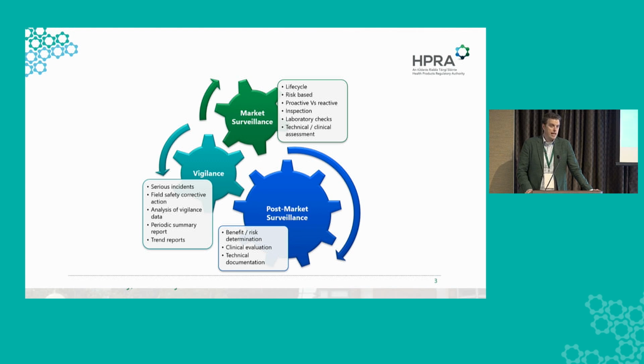So this is really how the manufacturer monitors the performance of their device once it's on the market. It really should be taken as a life cycle approach over the entire lifetime of the device. So it needs to look at the device from end to end, from day one that it enters the system to the day it leaves the system. And it needs to feed back into the risk management for the device. And I'm going to talk about that in a little more detail because it is absolutely key to the functioning of the system.